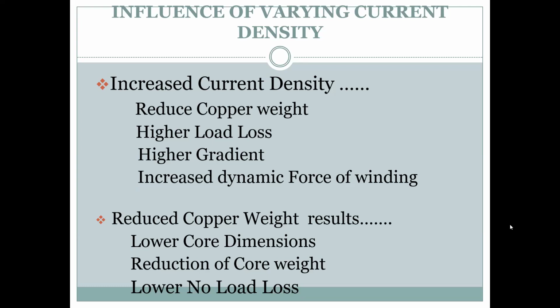Now, temperature gradient is very interesting. Your 50-degree temperature might be your optimum point, but between your lowest temperature and the highest there is also a gradient. You cannot keep 10 degrees like that. Your coldest point and the hottest point should not differ by more than 4 to 5 degrees. So you have to design that way, not only for the final figures, but for the entire winding. Of course, there is a reason: the transformer should be healthy enough. There should not be any hotspot developing somewhere that will spoil the insulation. So reduced copper weight results in lower core dimension, reduction of core weight, and lower no load loss. These are the advantages and disadvantages we have to play with in the design.